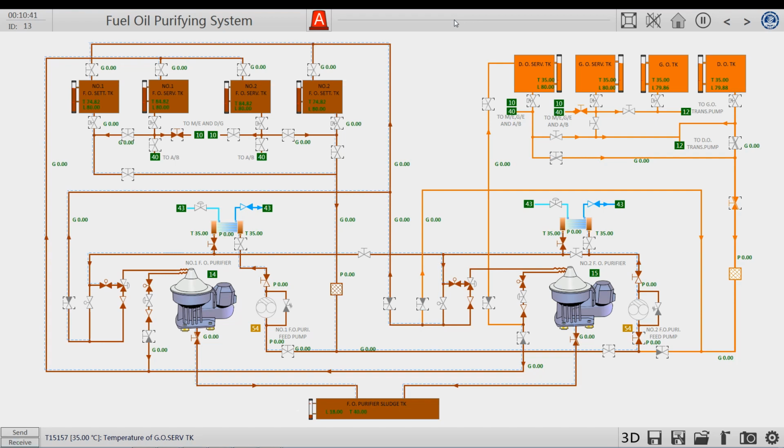If light oil is separated, open the valve associated with light oil. But there's a slight difference about the bypass lines from heavy oil. Light oil return is delivered directly to the inlet of the oil pump. And the reason for that, there's only storage tank in light oil system, but no settling tank. So it is more convenient to directly transport back to the oil pump inlet. This is the difference between the number 2 separator and the heavy oil on the light oil bypass lines.